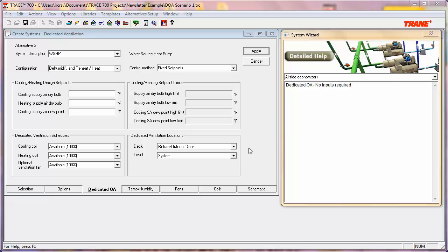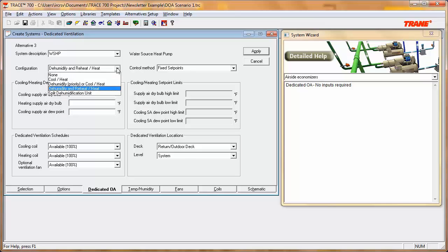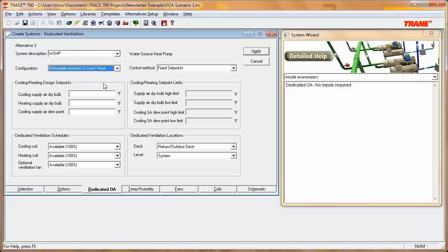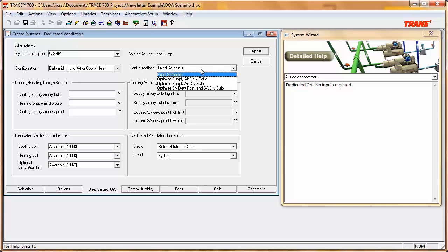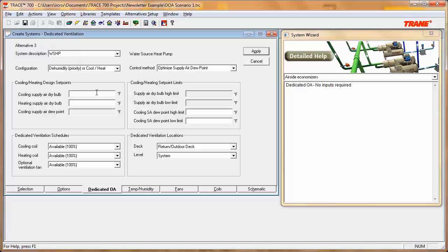Going back into TRACE to model this scenario, on the Dedicated OA tab we need to change the configuration from dehumidify and reheat to dehumidify, or cool/heat. We also change the control method from fixed set point to optimized supply air dew point. For cooling supply air dry bulb, we enter 60 degrees; for heating supply air dry bulb, 68 degrees. The high limit on the dew point is 60 degrees and the low limit is 52 degrees. Ventilation schedules remain at 100% available, and the dedicated ventilation location stays as return outdoor deck at system level.